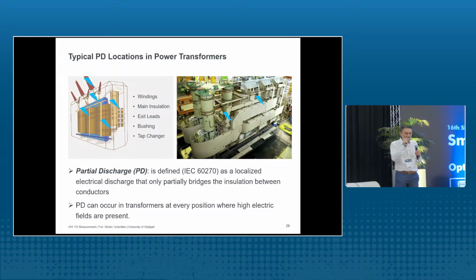So let's say you have a flashover in the air very near to the high voltage electrode, but you do not have a full flashover to ground. Yeah, so it's just a partial discharge. And these partial discharges, of course, can also occur inside the transformer tank in, let's say, almost all positions where we have high electrical field strength. So here you can see an active part. You can have these partial discharges at the lead exits, also within the windings, at the tap changer. Yeah, so there are different possible locations of partial discharges.